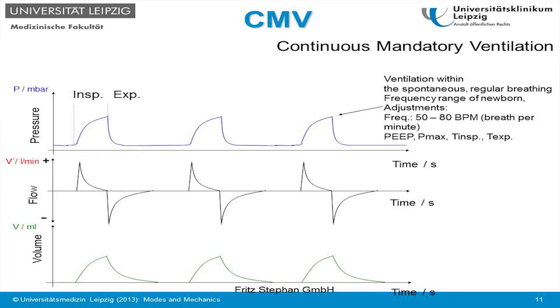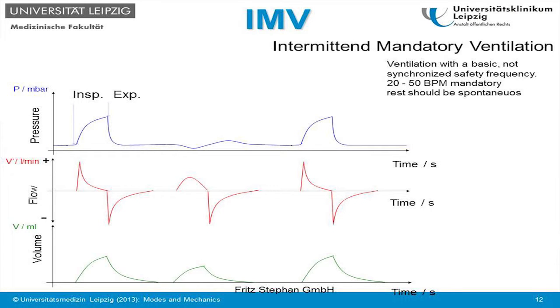When we lower the frequency, the patient can have own breath in between. We see this on this graph here. This is a machine breath. Then the patient initiates his own breath. The patient takes away air from the circuit. So we see a little pressure drop even, and the patient has an inspiratory flow, followed by an expiratory flow. Here's the volume of the lung during the spontaneous breath, and here is the next machine breath.